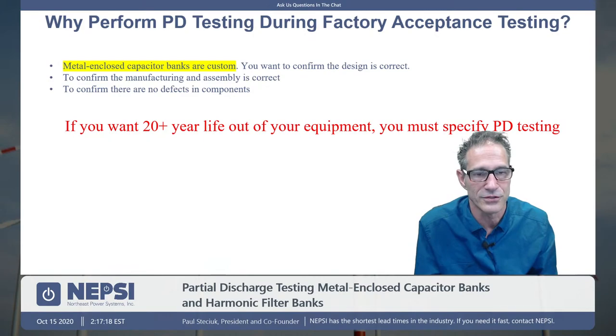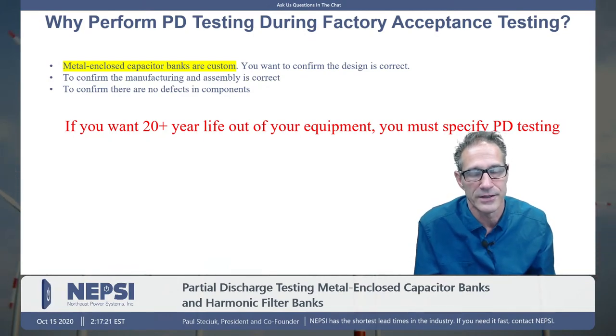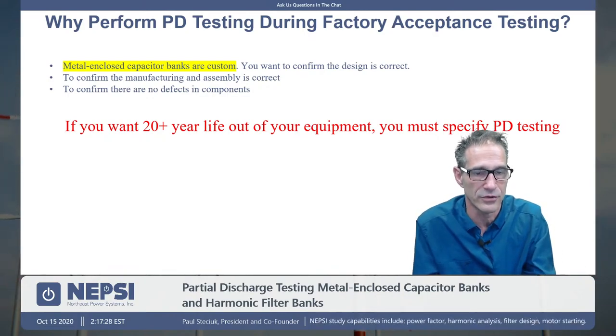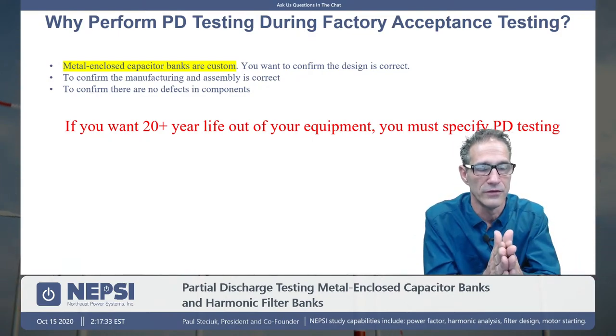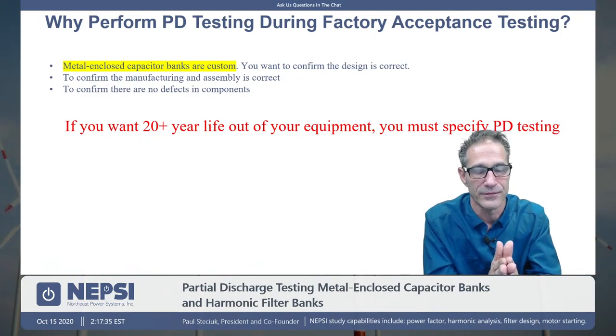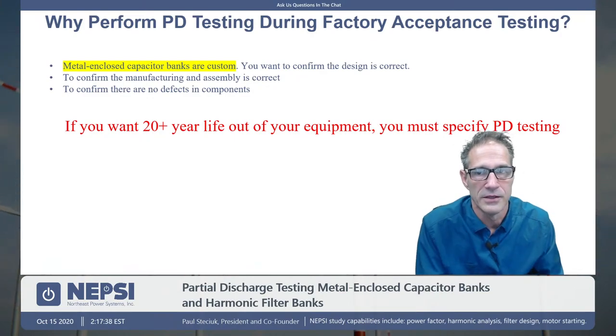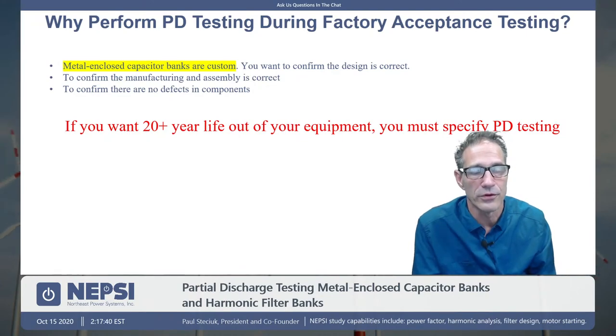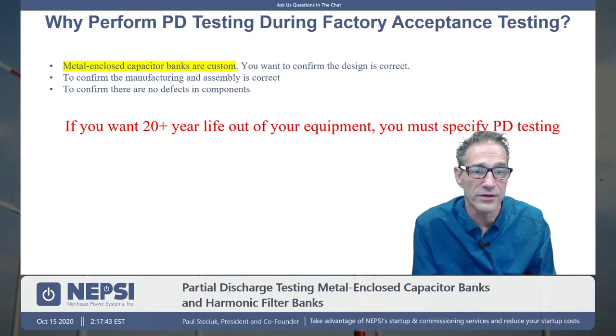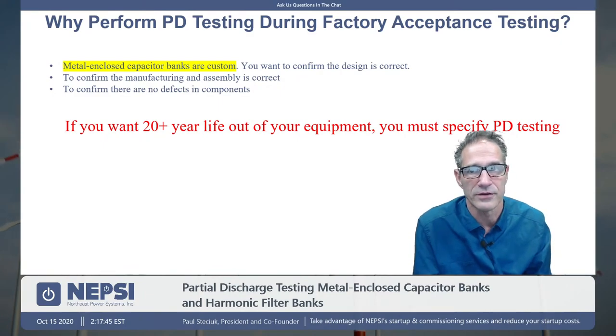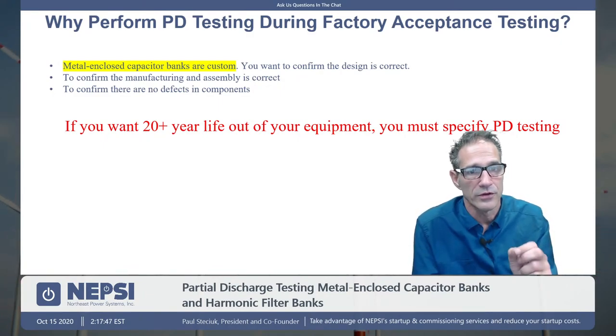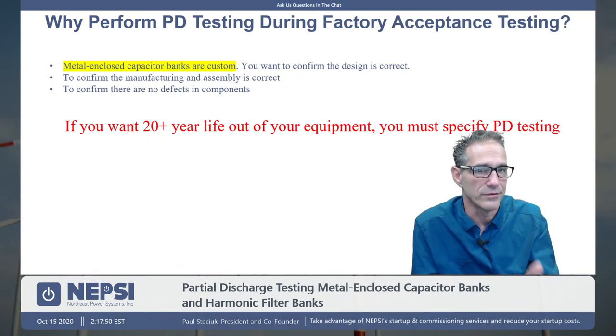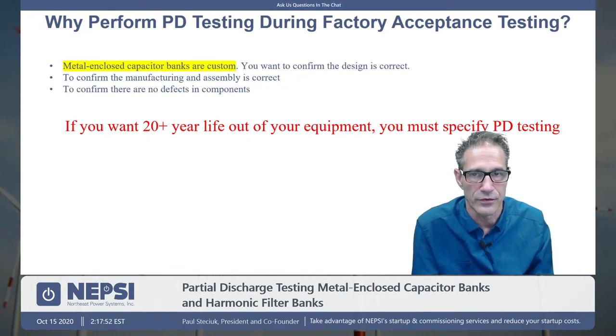And a partial discharge test would help to pick up on whether there is a defect in that design or not. Did they lay, for instance, that jumper cable onto the ground when it was supposed to be put on an insulator? Or did they bring two medium voltage jumper cables of opposite phase together when they shouldn't have? These are things that we can pick up on. So it's important to do, not only to confirm the design, but also to confirm the manufacturing process. And you also want to confirm that there are no defects in the components, the bushings, and so forth.